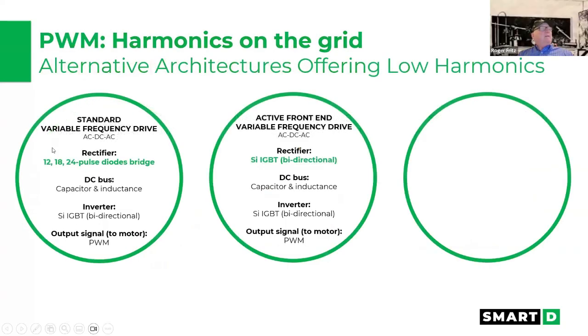So then they've moved the VFD where they actually put in more diodes. They've got 12 pulse, meaning 12 sets of diodes, 18 pulse, and 24 pulse. And what that does is it mitigates some of it, but you have to have a transformer that steps it to the 12 pulse and the 18 pulse. So you have multi-step transformers, and that becomes very expensive. Again, you still have the PWM out to the motor.